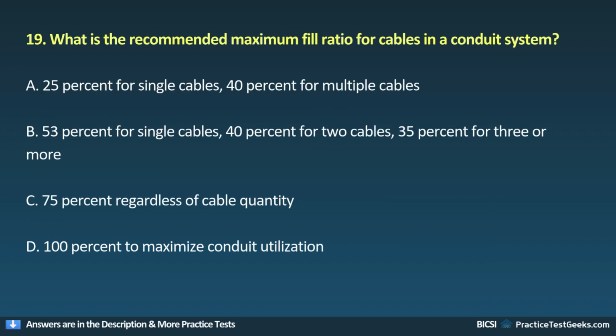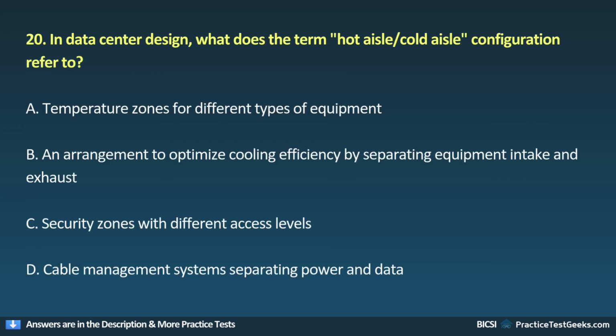19. What is the recommended maximum fill ratio for cables in a conduit system? A. 25% for single cables, 40% for multiple cables. B. 53% for single cables, 40% for two cables, 35% for three or more. C. 75% regardless of cable quantity. D. 100% to maximize conduit utilization.